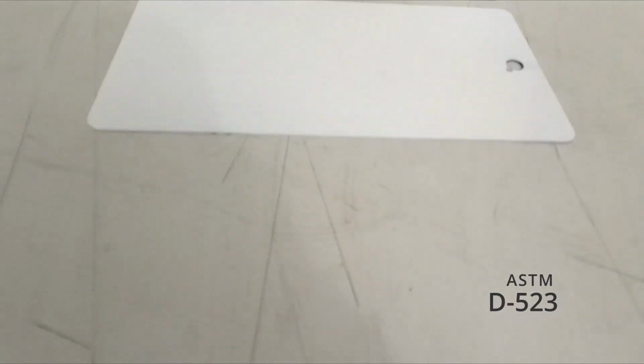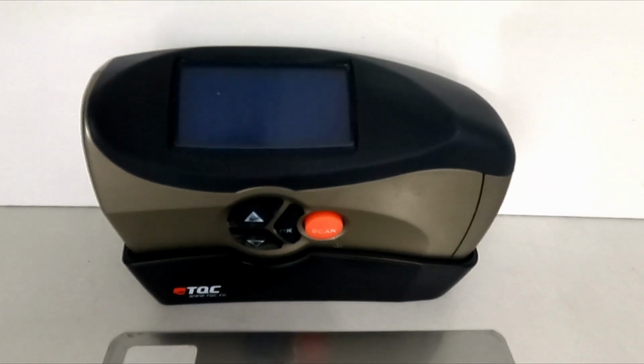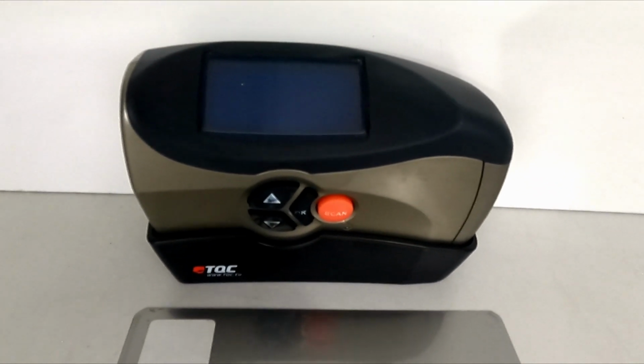On today's Look in the Lab, we are going to be covering gloss per ASTM standard D-523. Gloss is an aesthetic property of a finished coating and is recorded in gloss units, a measure of how reflective or shiny the surface of a coating is.